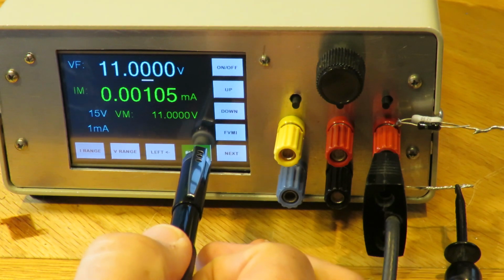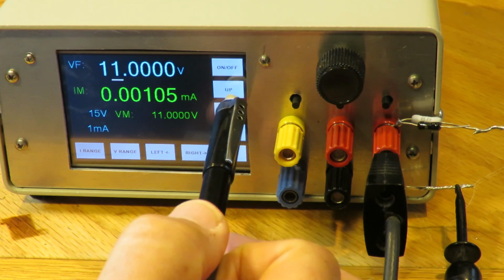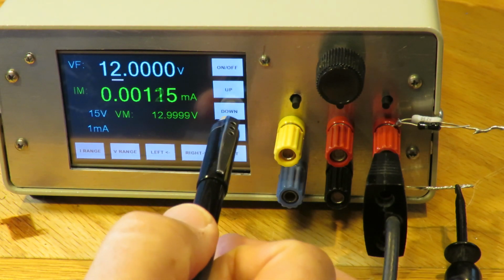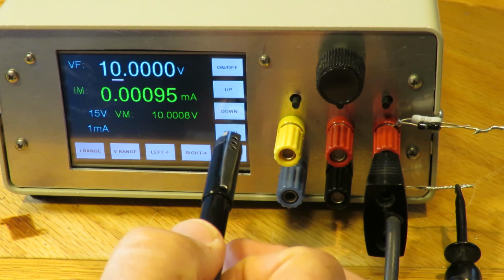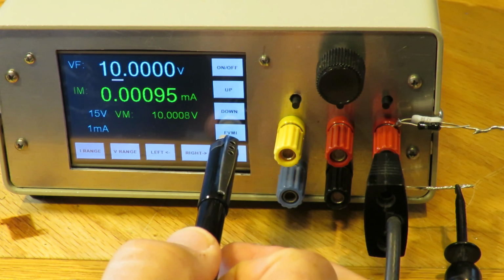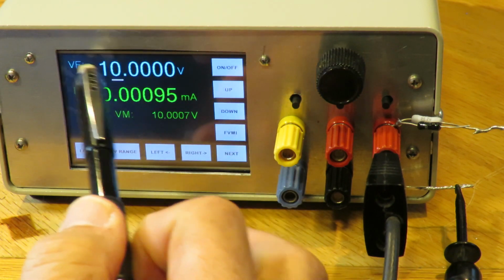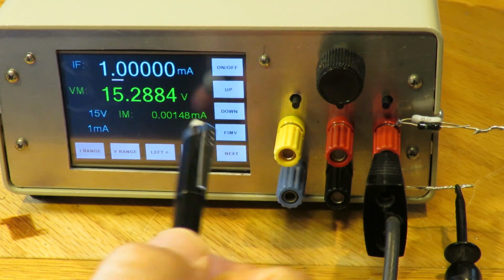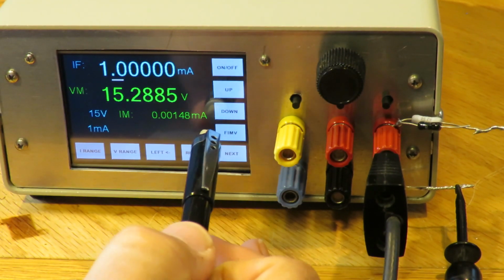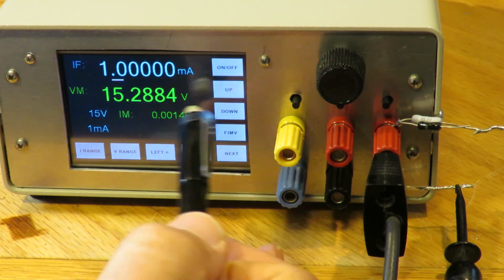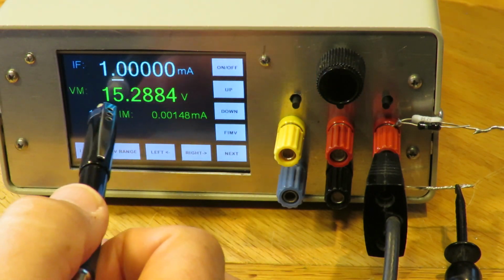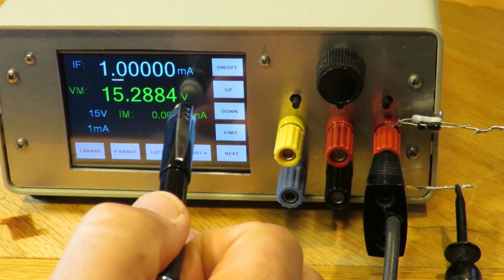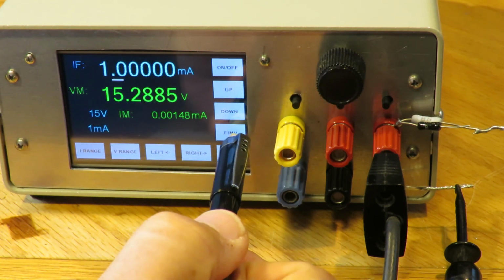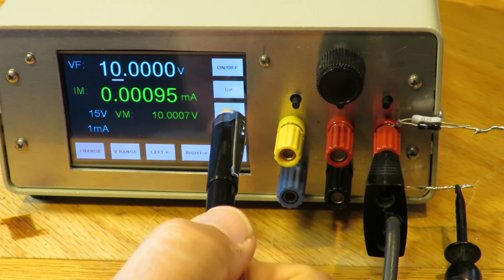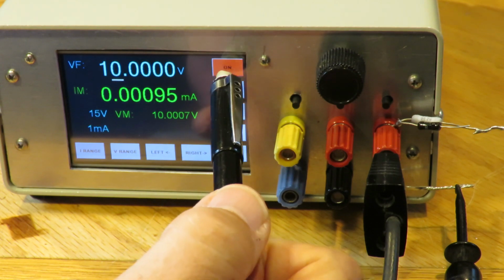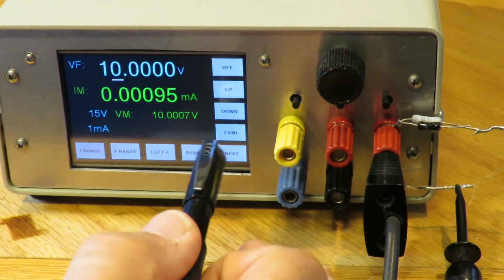These 2 buttons control the cursor position, left and right. These 2 control the value, up and down. This button controls whether it's, right now it says FVMI, which is force voltage measure current. So I'm forcing a voltage and measuring a current. When you hit the button, then it goes to force current and measure voltage. It's on the 15 volt range, so it goes to full voltage, whatever the voltage clamp is set to, which is currently 15 volts. And there's an on-off button, which is currently not implemented, so the output is always on.